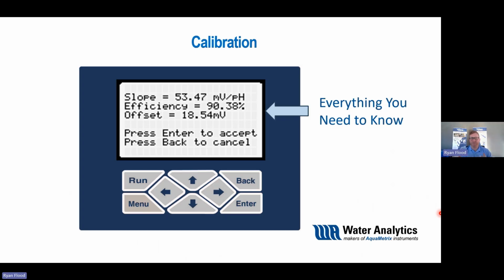Now, just because it's at 90% efficiency, 90% efficiency is still really strong and can get you good readings. When you go through your process more and more, you can see how consistent these numbers are. As your efficiency starts to go down over time, that can also be your early indicator that you may need to perform some maintenance sooner rather than later.